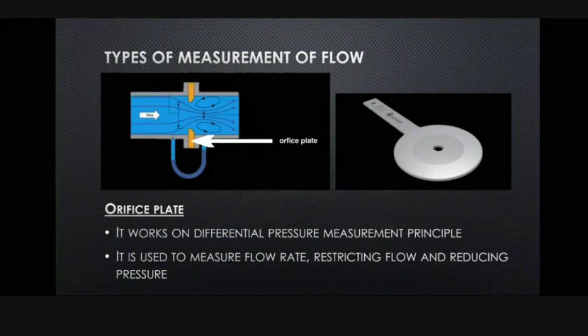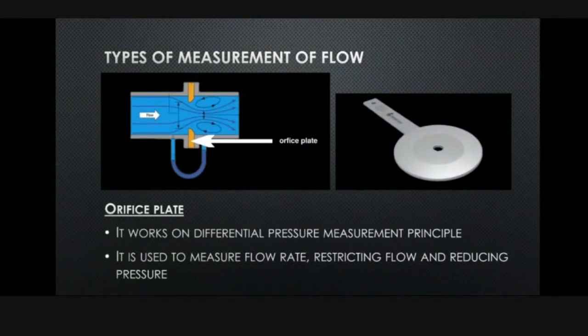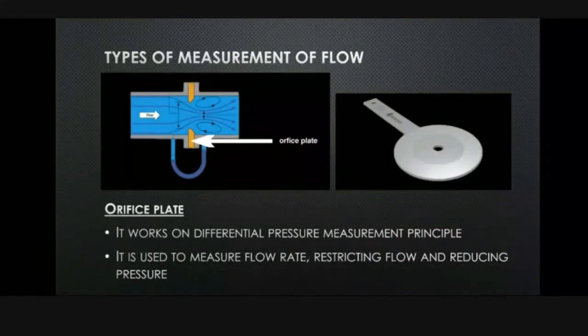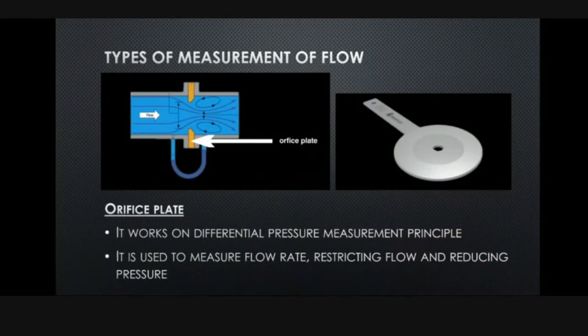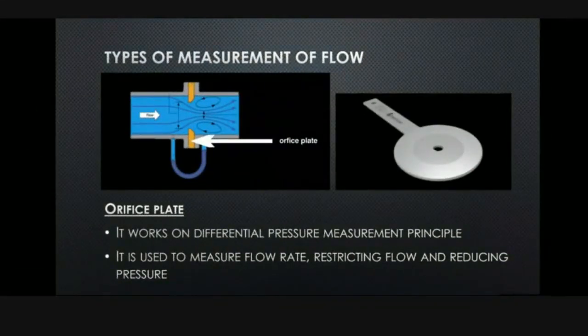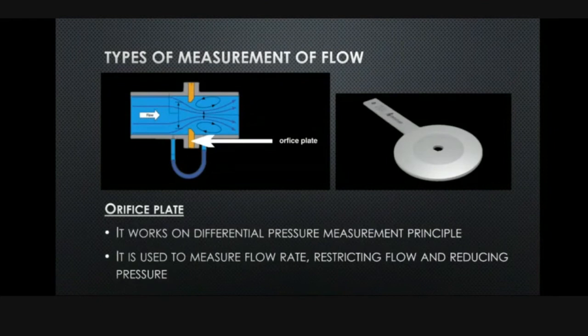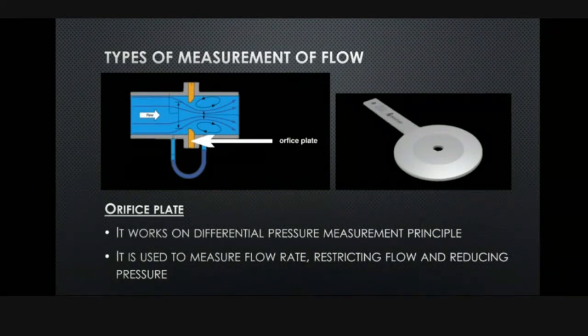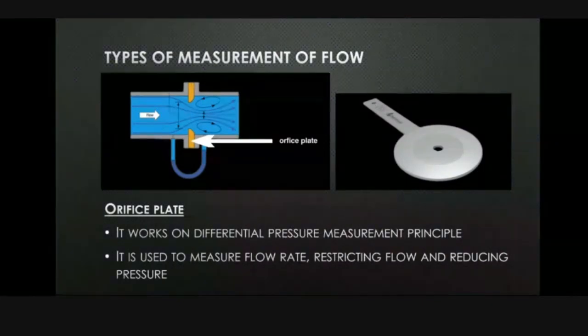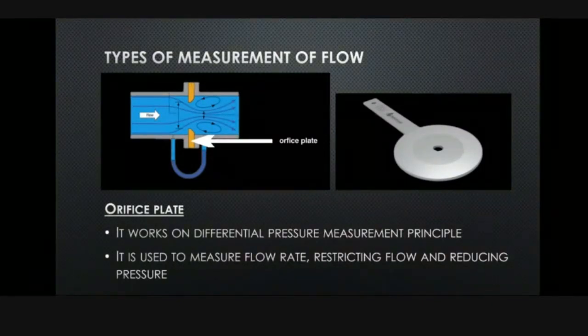At the bottom of the curve, there is the meter, which shows the details of how much pressure is being released. And if we talk about its application, it is used in oil filtration, petrochemicals, and refineries, as we saw in the first slide. Its advantages are it's quite cheap, requires less space, and can be installed vertically, horizontally, or inclined. Its disadvantages are it can get clogged, and 40 to 90% of head loss or differential pressure can occur.